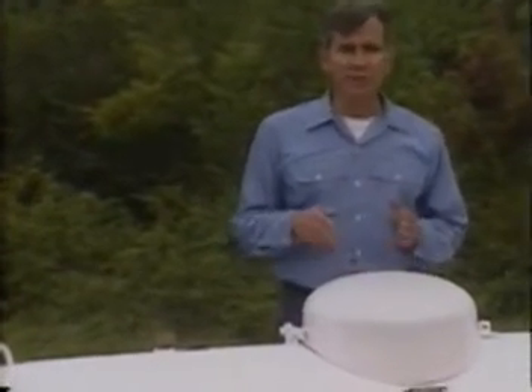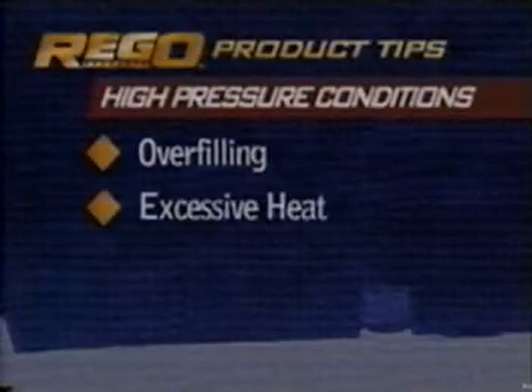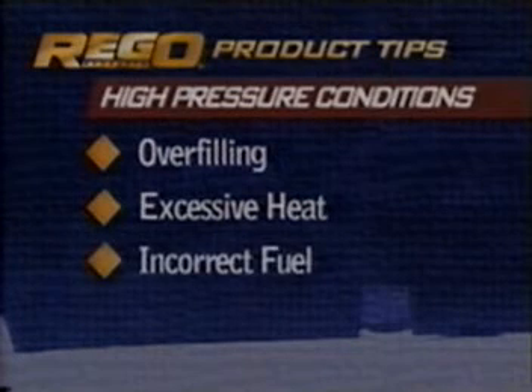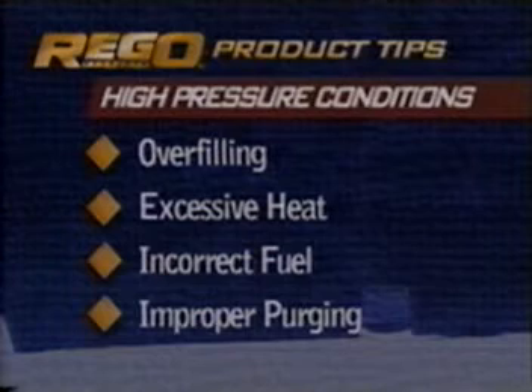The pressure relief valve is designed to protect the container from catastrophic failures caused by extremely high pressures. These hazardous conditions can result from overfilling, exposure of the container to excessive external heat, the use of incorrect fuel, or improper purging of the container. Proper purging instructions can be found in the REGO serviceman's manual.